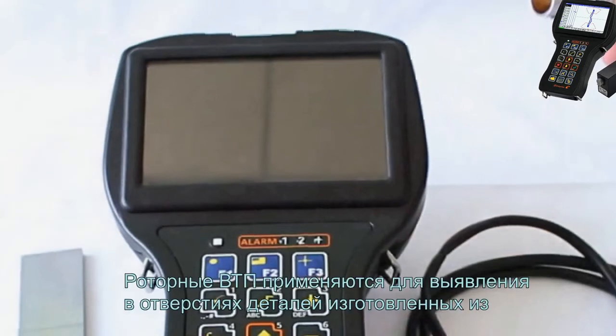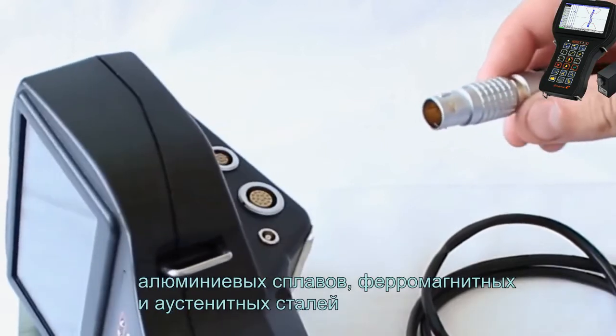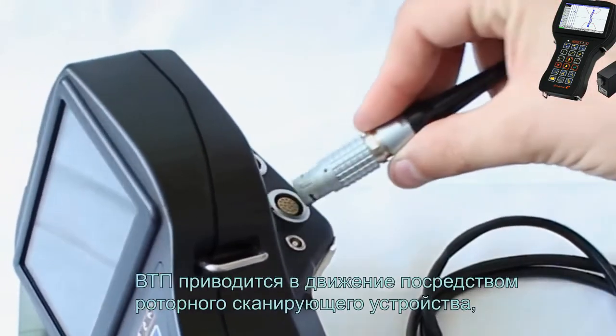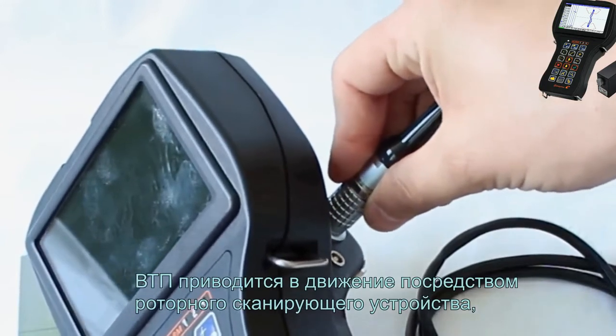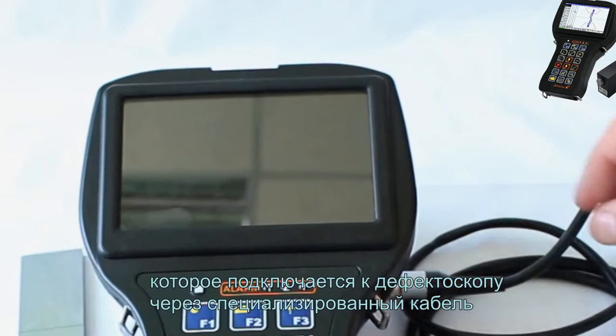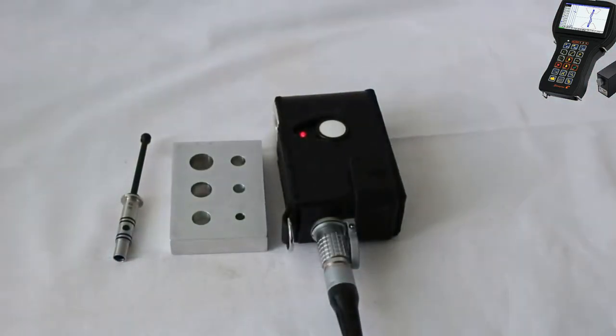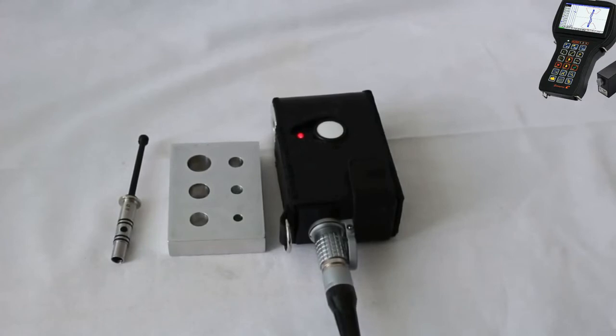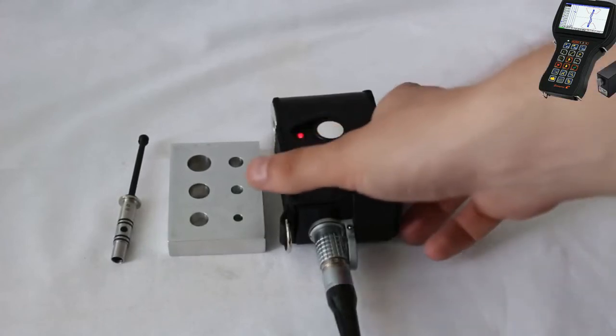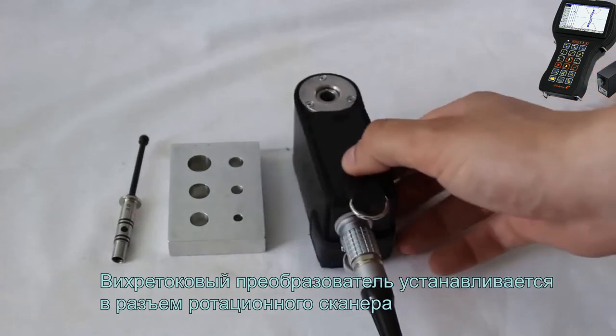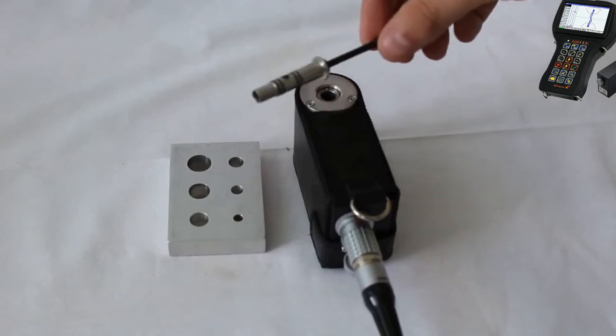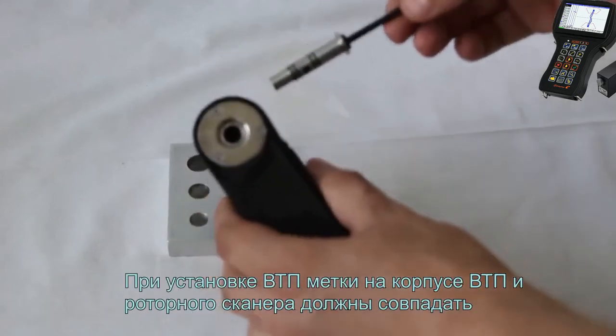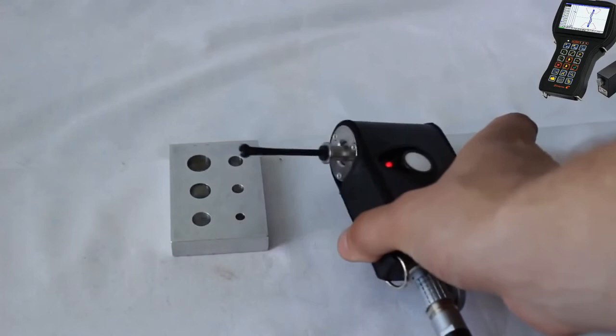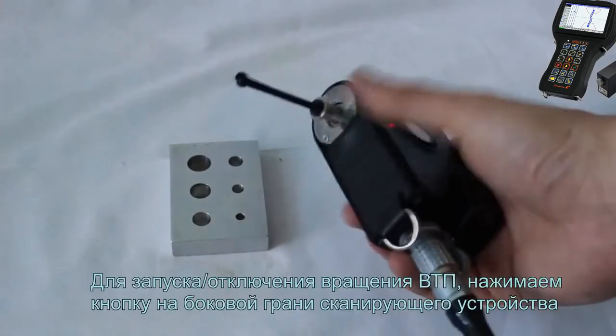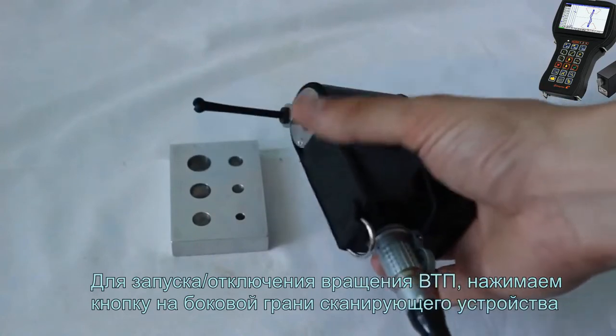Rotary EC probes are used for defects detection in test with holes made of aluminum alloys, ferromagnetic and austenitic steel. EC probes are driven by the rotary scanner, which is connected to the flaw detector through the specialized cable. The EC probe is inserted into the scanner connector. When inserting the EC probe, make sure that the marks on the probe housing and rotary scanner have been matched. When inserting, press the probe until tight. To stop the probe rotation, press the button from the side face of scanner.